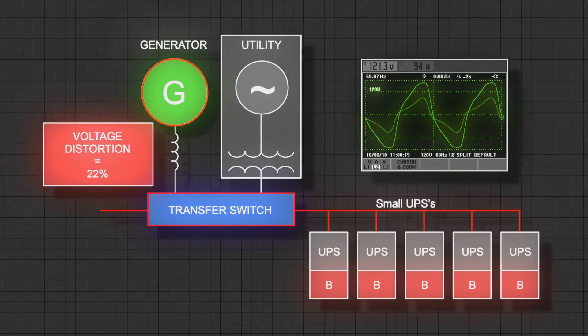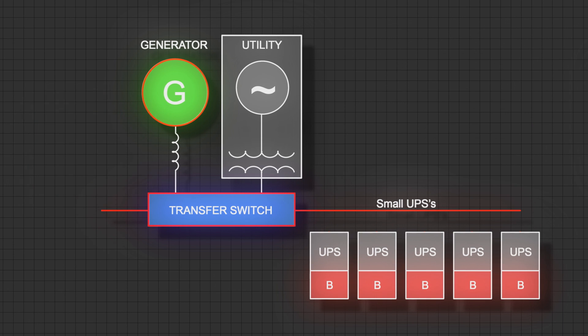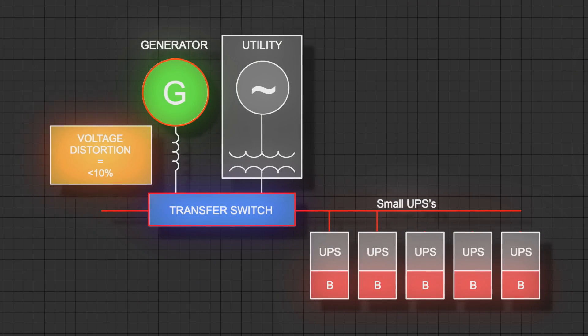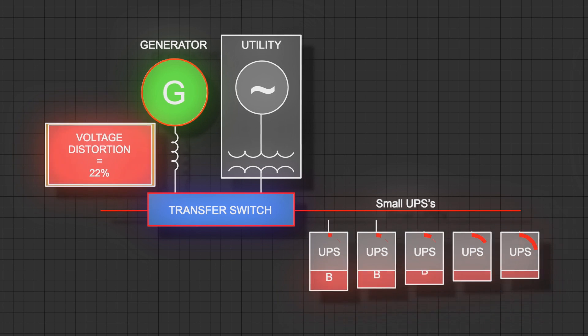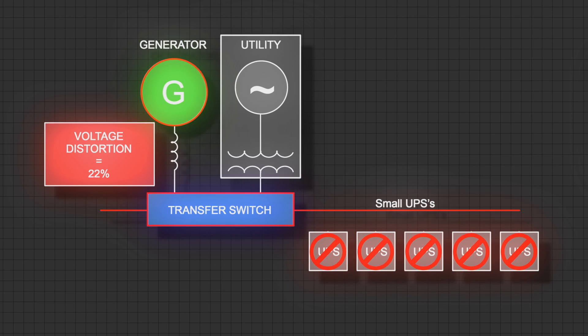The voltage distortion on the 120-volt UPSs went from 3% distortion on the utility source to nearly 22% distortion on the generator. Isn't that high for voltage distortion? Yes, extremely high. The UPSs determined that wasn't an acceptable voltage and transferred back to battery. Once enough of the UPSs went to battery, the voltage cleaned up and the UPSs decided the voltage was okay, so they went back to the generator source. Again, when enough UPSs came on and began charging batteries, the cycle repeated until the UPS batteries died and the load was dropped.